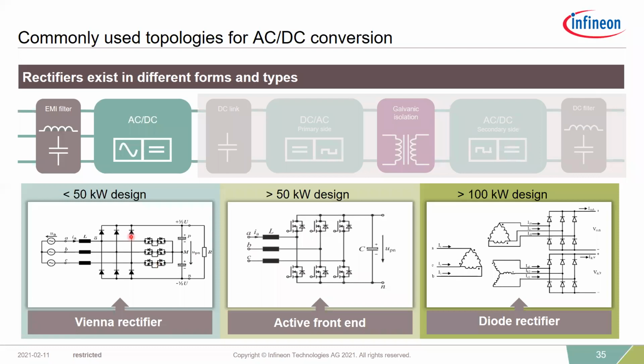Of course, the shortfall of this Vienna rectifier is that bidirection is impossible. When you go for more than a 50 kilowatt design, handling such high power in a three-level topology is highly cumbersome. That's the reason active front end is the clear direction. In this case, you can quite easily implement the bidirectional feature as well.